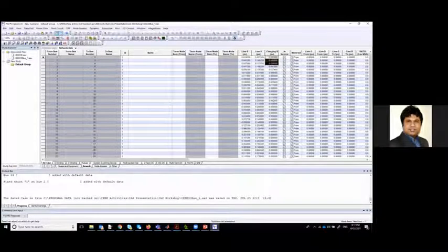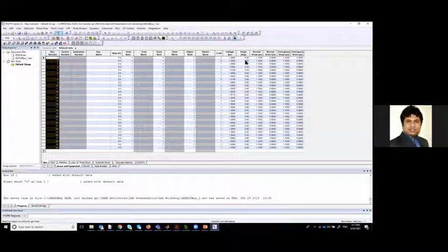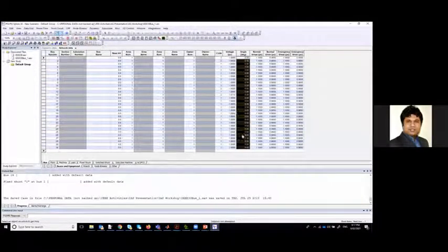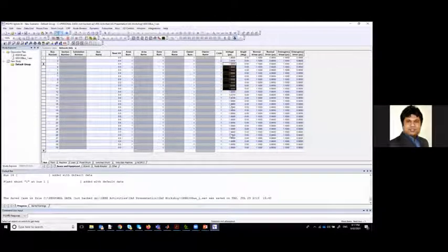If we do the power flow, again, if we go back and look at the power flow, look, all these angles are 0, 0, 0, okay? All these are 1, 1, 1, 1, 1, or something like that. Some of these, 5, 8, 11, 13, are different. At 5, it's 1.01. But if you look at 11, it's 1.082. And 13, it's 1.07, okay? So these are given here.